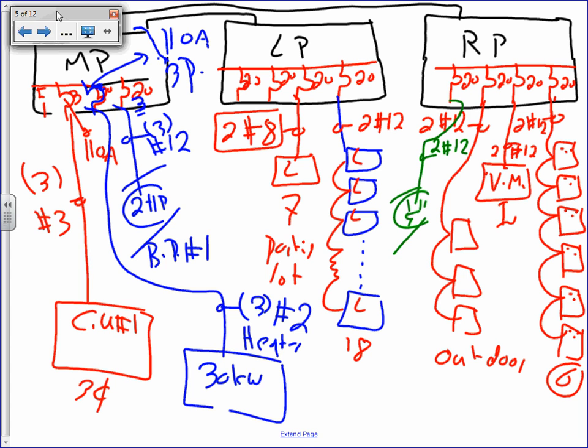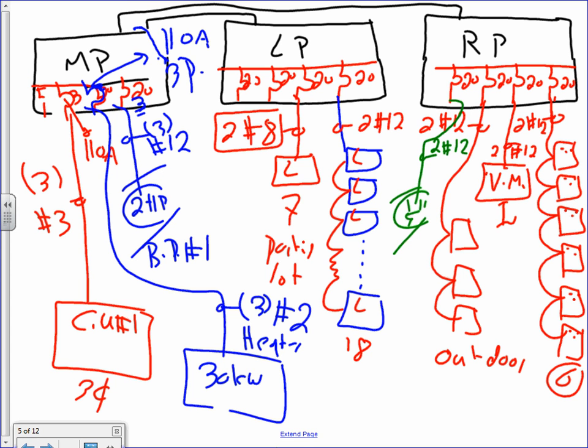Now, here's the judgment. I have the main panel, the receptacle panel, and the lighting panel. And I gave you guys suggestions. Let's start from here, receptacle panels. On a 20 amp circuit, 2 conductors number 12, you can fit 6 receptacles. Why? Now remember, we are feeding receptacles in an office type building. You're going to see why 6 in a second. Can I have thumbs up, Chad? We understand that 6 of them fit here.